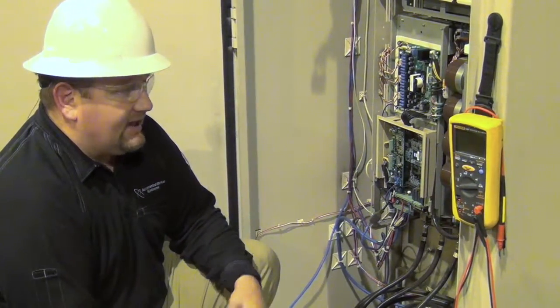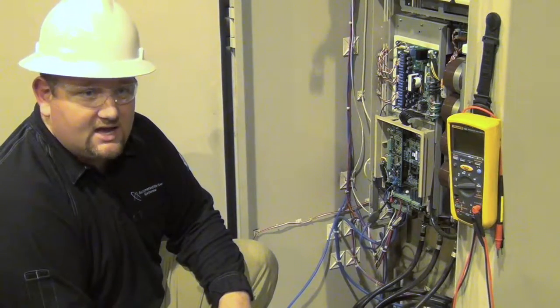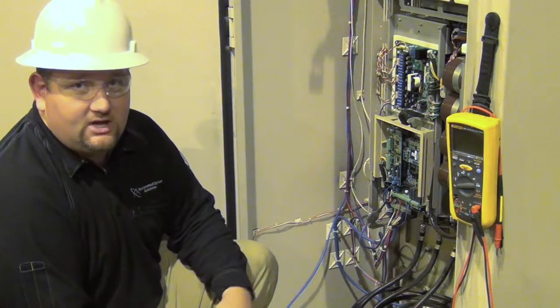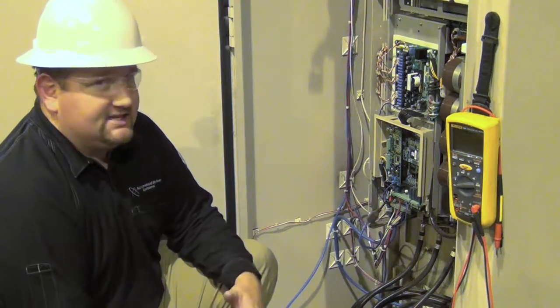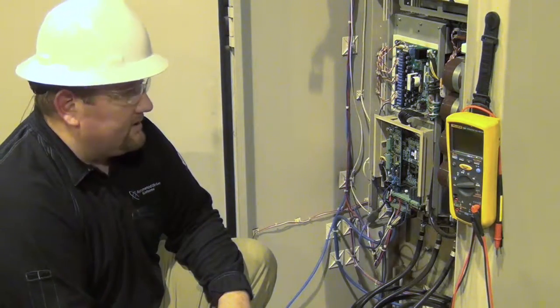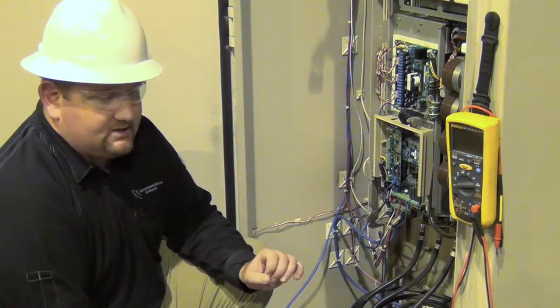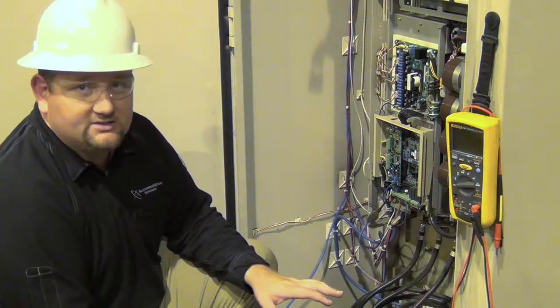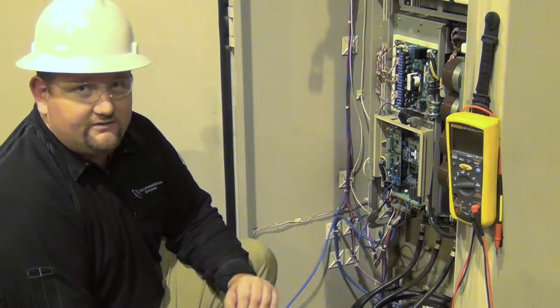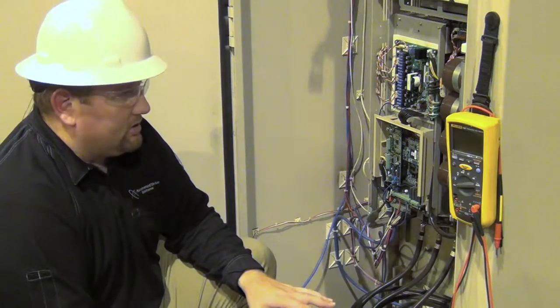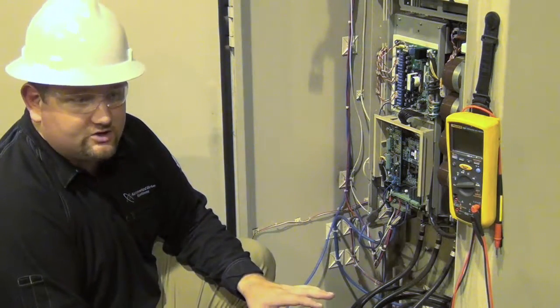We get calls a lot where cooling fans have locked up, where the drive just gets so caked with dirt over a period of time that the heatsink can no longer keep itself cool. Some really basic vacuuming it out, light air compressor use, blowing the dust off, keeping things clean, keeping things cool, really help ensure a good long life for your drive.